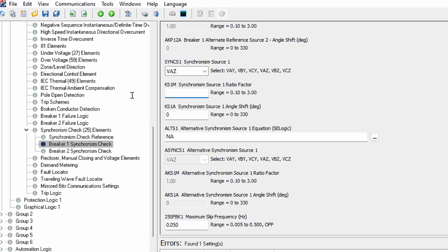Now we also have 2 more settings over here, which are for magnitude and phase angle compensation. And since we are using the phase to neutral voltages of A phase for both the reference voltage and the synchronizing voltage, we do not need to use them in our case. So we can leave that at 1 and 0. But let's actually go through an example just to see how you would use those settings if you had a different synchronizing voltage than you did for the reference voltage.